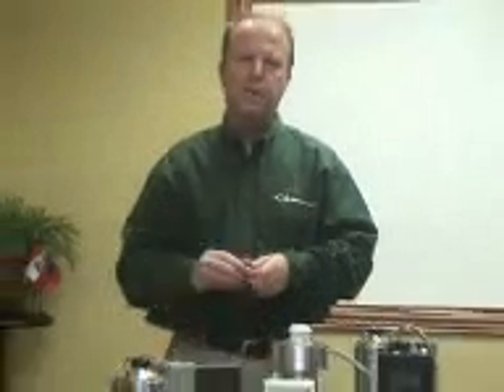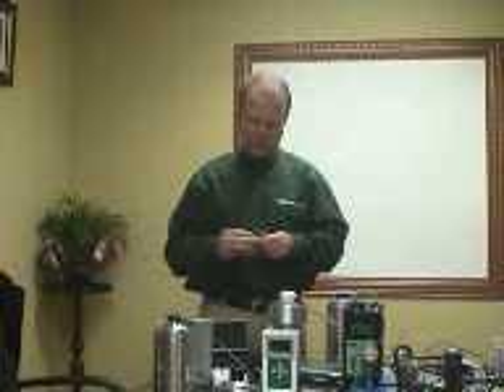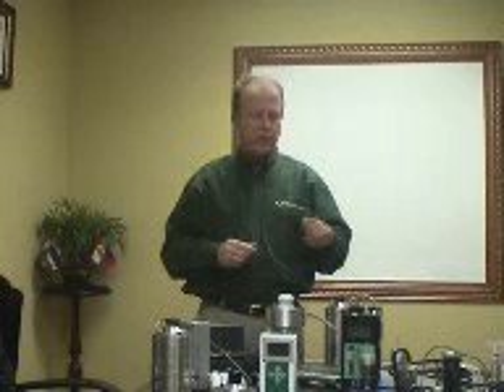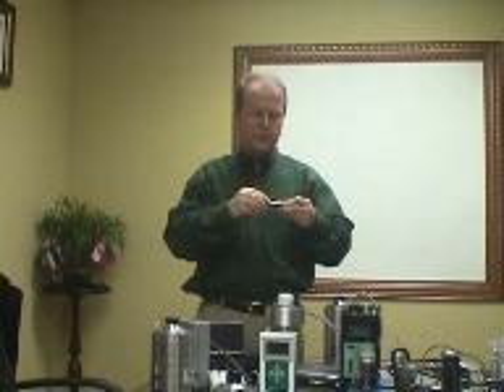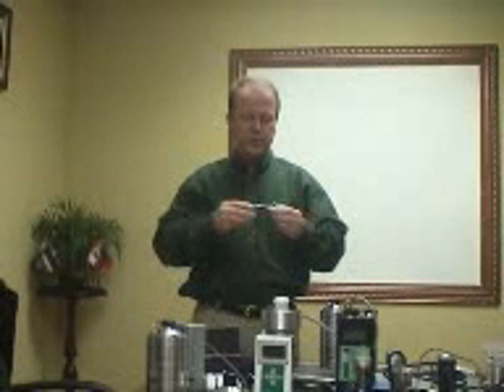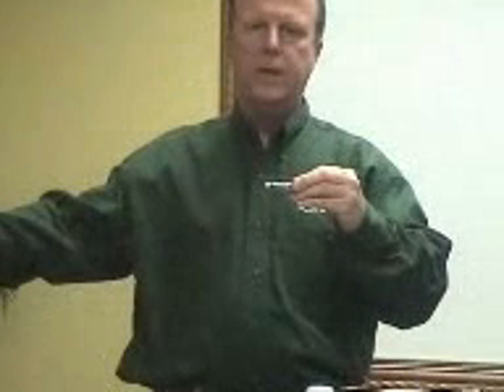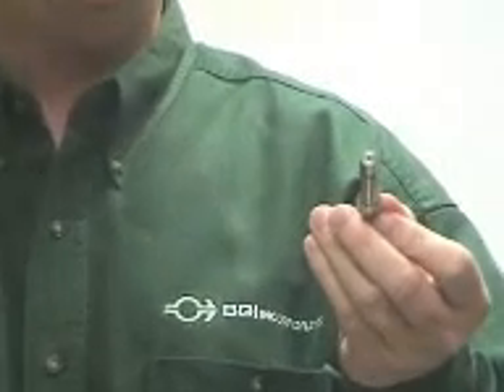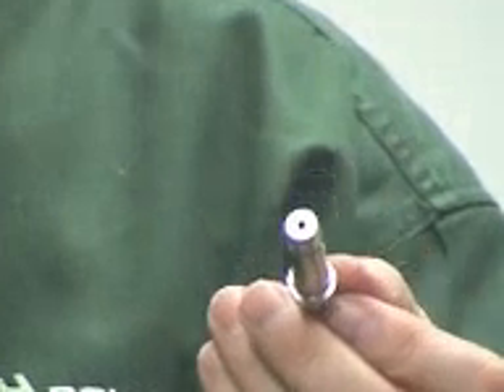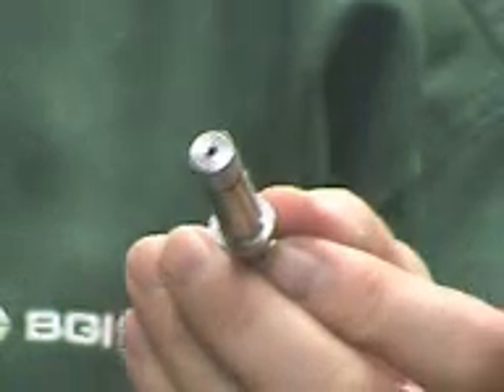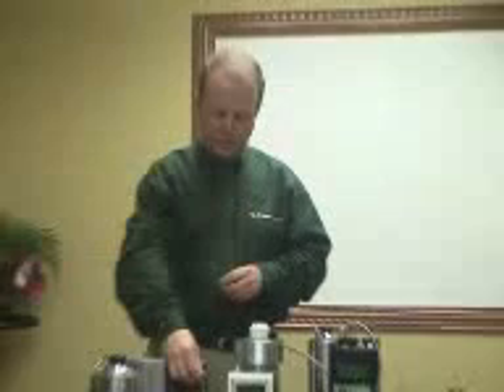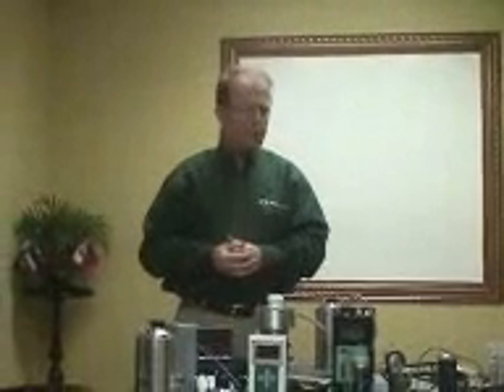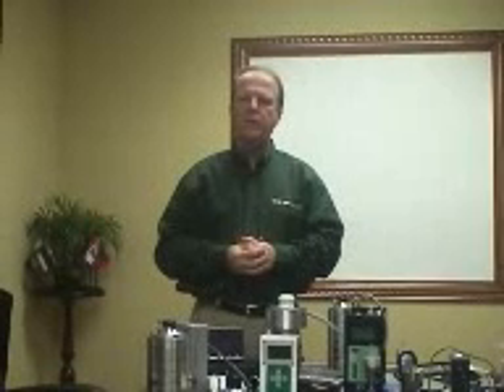Or if you want to have special orifices made for your particular flow rate, BGI will build those for you. You thread the orifice onto the end of the hose barb. You slip your vacuum hose over each end and connect it to the pump, and in this case, you would be controlling the flow at 24 liters a minute by pulling half an atmosphere of pressure across this orifice. Very simple mechanical devices that have been used for 50 years.